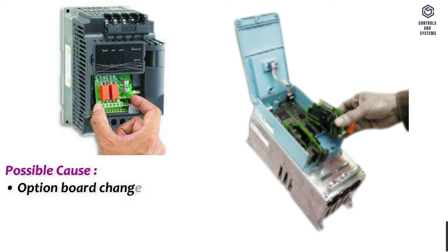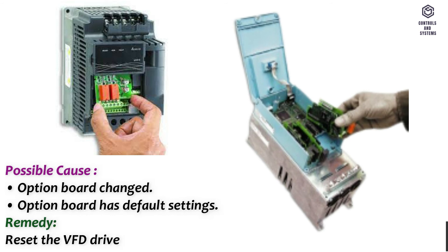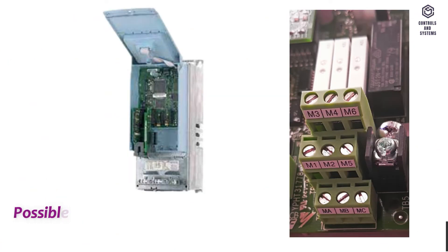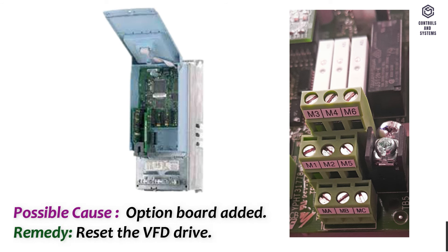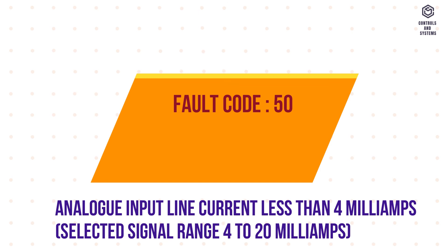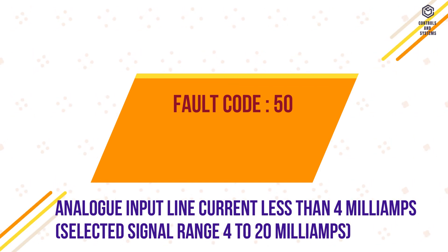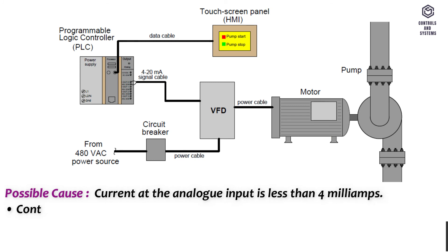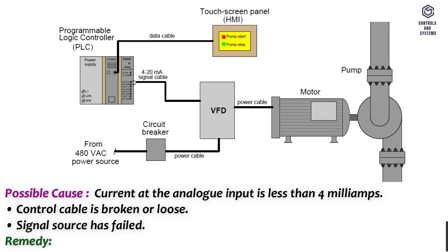Fault code 44 – Device change. Possible cause: option board has default settings. Remedy: reset the VFD drive. Fault code 45 – Device added. Possible cause: option board added. Remedy: reset the VFD drive. Fault code 50 – Analog input line current less than 4 milliamps (selected signal range 4–20 mA). Possible cause: current at the analog input is less than 4 milliamps; control cable is broken or loose; signal source has failed. Remedy: check the current loop circuitry.